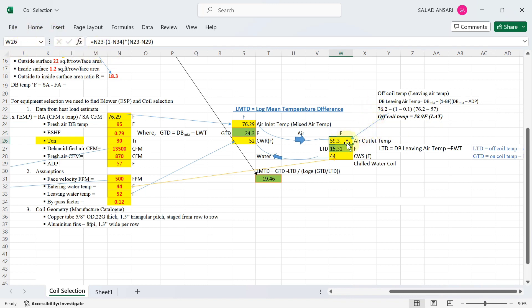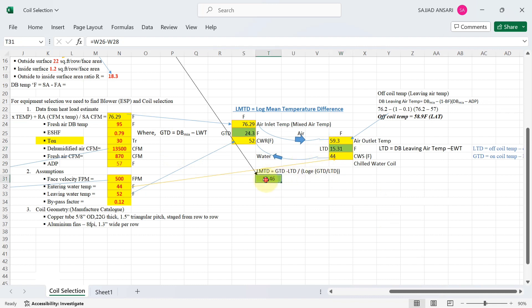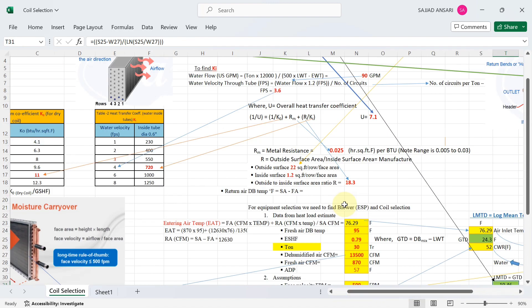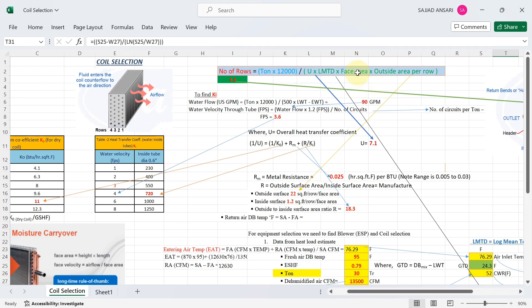The off-coil temperature calculates to approximately 59.3°F. Entering water temperature is assumed at 44°F. When you calculate LTD and apply the LMTD formula with GTD and LTD, you get an LMTD value of 19.46. This is your log mean temperature difference.